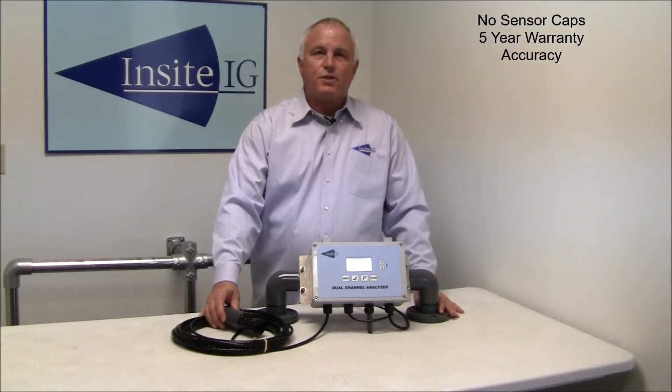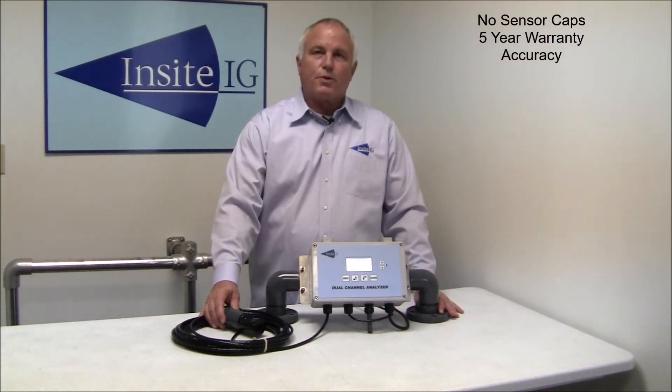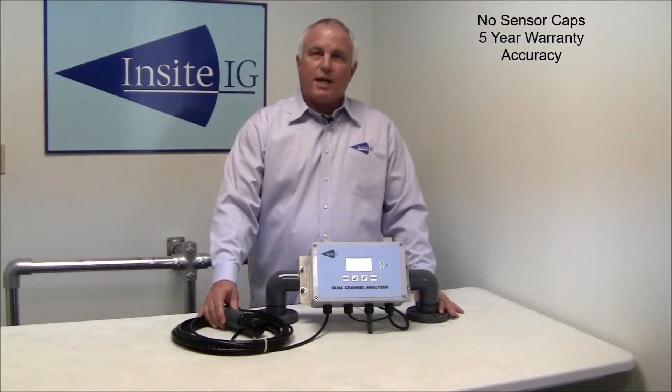The Insite sensor accuracy is plus or minus zero point zero five milligrams per liter across the entire range of the sensor. Sensor drift is less than one percent per year. The sensor is so accurate we recommend sensor calibration on about the same schedule as the competitors recommend completely replacing the sensor cap. We have customers actively controlling DO levels with a total operating span of 0.1 milligrams per liter and less.